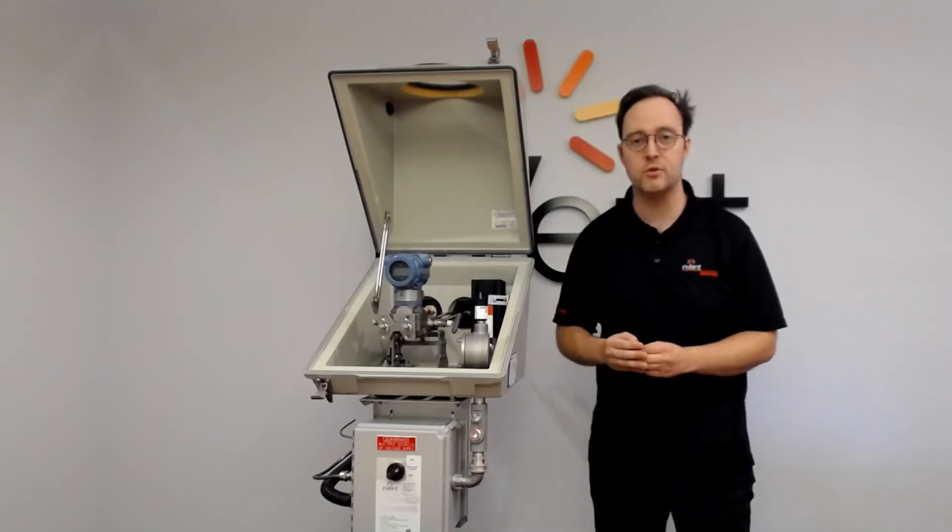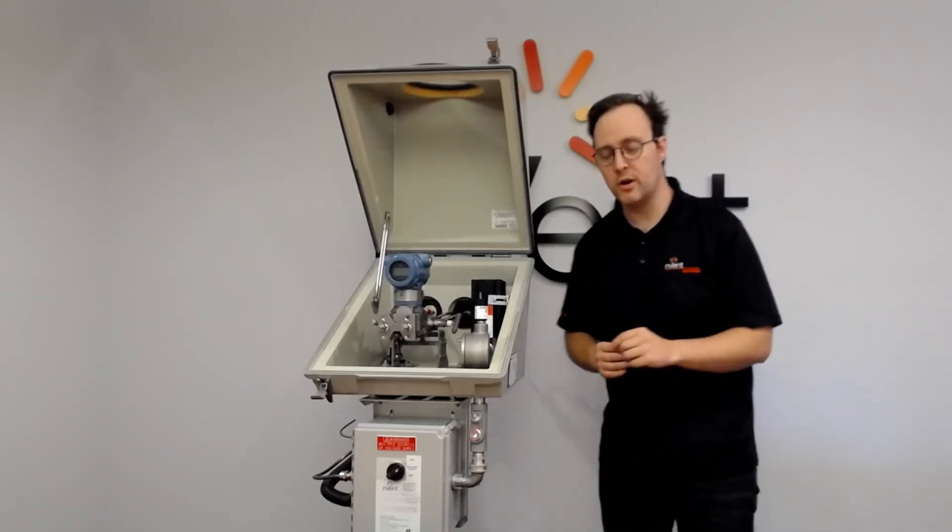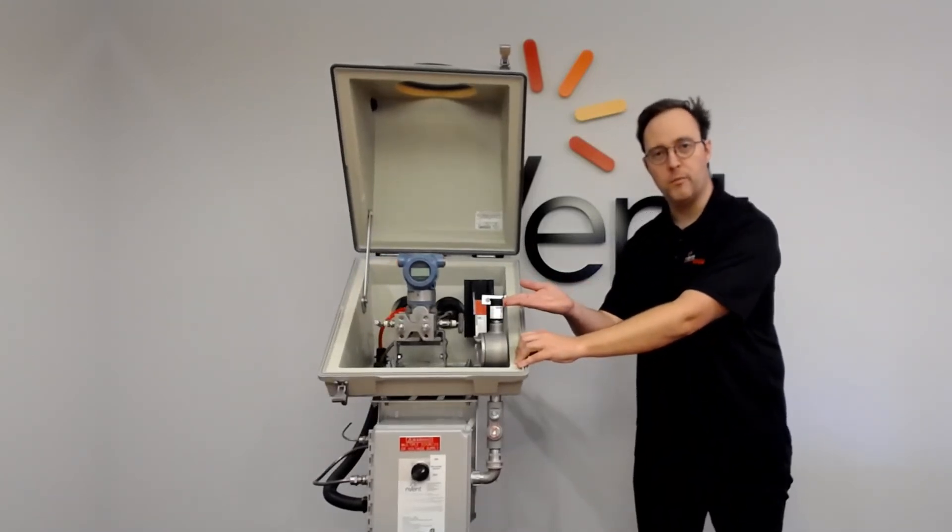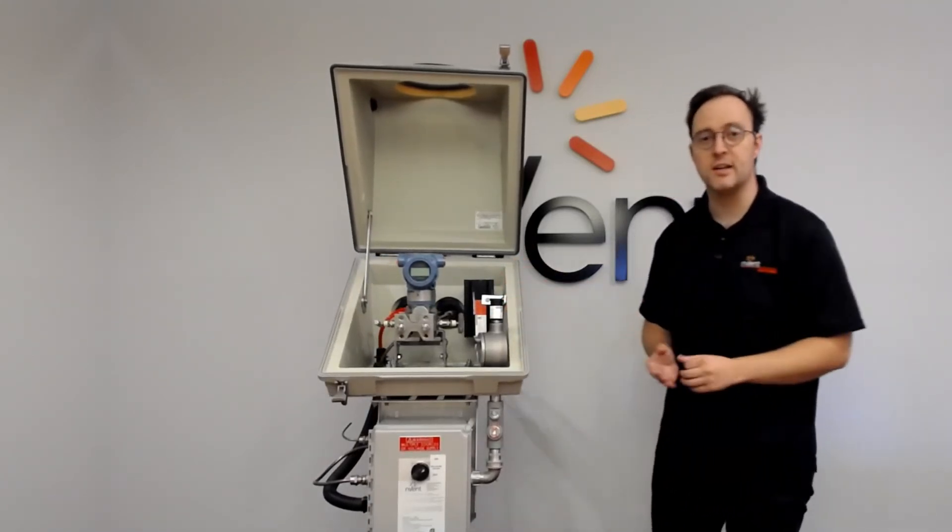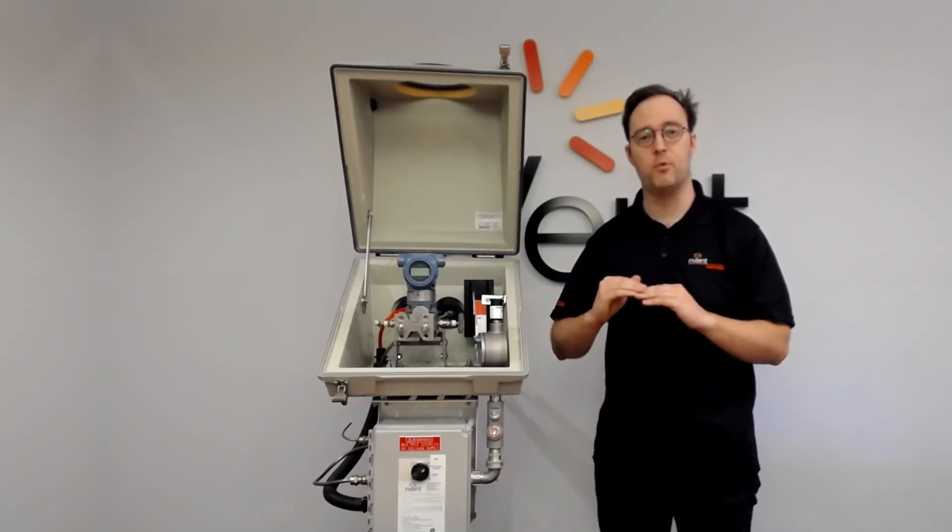For an enclosure this size in freezing temperatures, you're looking at about 100 to 150 watts. You also want to consider that you want to have a control mechanism. In this case, a thermostat to ensure that the inside temperature stays at where your customer specified the set point to be.